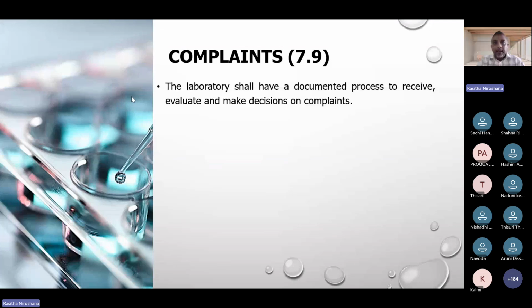And then some people use a fishbone and all information is given. So you need to monitor that, right? You need to monitor that. So then the investigation part, and then deciding action, tracking and recording the complaint, including actions undertaken to resolve it, ensuring that any appropriate action is taken. For example, if your organization is certified for 17025, you can track up to the person who has done the testing. Or maybe that person can keep the retained sample. So that can be part of that. But everything has to be documented.